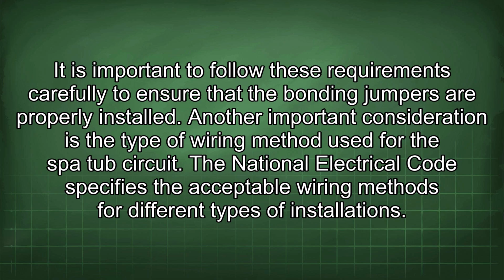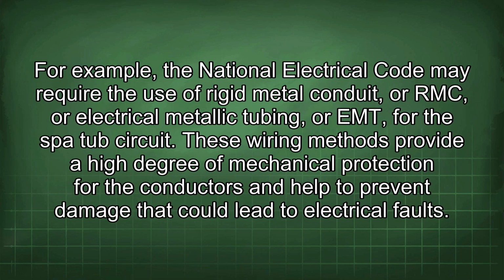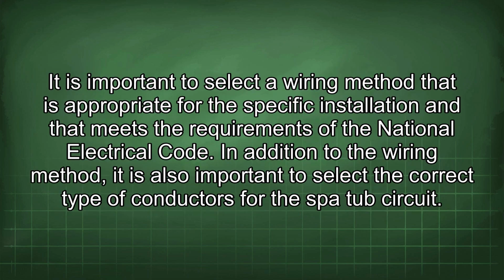Another important consideration is the type of wiring method used for the spa tub circuit. The National Electrical Code specifies the acceptable wiring methods for different types of installations. For example, the National Electrical Code may require the use of rigid metal conduit, or RMC, or electrical metallic tubing, or EMT, for the spa tub circuit. These wiring methods provide a high degree of mechanical protection for the conductors and help to prevent damage that could lead to electrical faults. It is important to select a wiring method that is appropriate for the specific installation and that meets the requirements of the National Electrical Code.